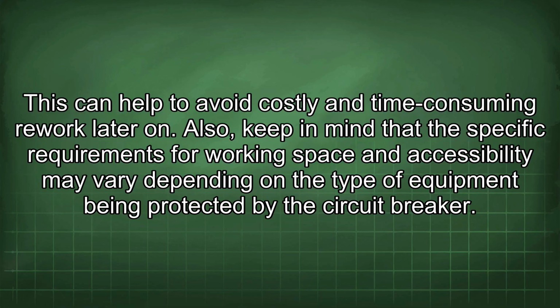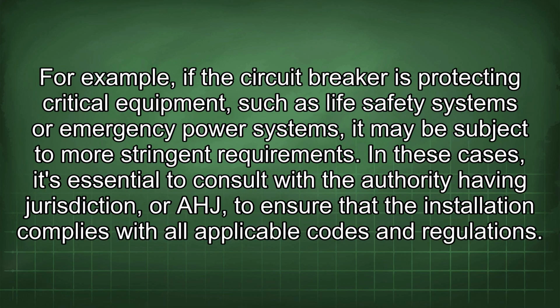Also, keep in mind that the specific requirements for working space and accessibility may vary depending on the type of equipment being protected by the circuit breaker. For example, if the circuit breaker is protecting critical equipment such as life safety systems or emergency power systems, it may be subject to more stringent requirements. In these cases, it's essential to consult with the authority having jurisdiction, or AHJ, to ensure that the installation complies with all applicable codes and regulations.